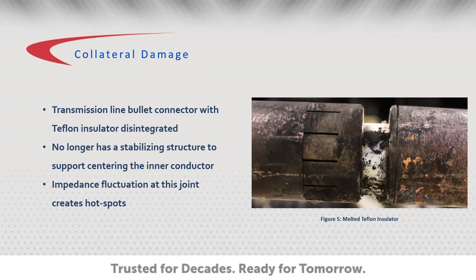Figure 5 here shows the anchor bullet connector with a melted Teflon insulator. In absence of the Teflon, the inner conductor was no longer stabilized and centered inside of the outer conductor. This allowed the inner conductor to move freely and caused a fluctuating impedance mismatch that eventually led to complete failure of the connected structure. The debris from the melted Teflon coats the inner conductor and littered the line below it. And the presence of the debris lowered the handling capability of the line.